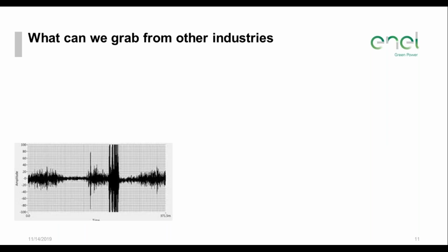For example, a very common technology in other industries is ultrasonic analysis. Using this tool, we can pick up the ultrasonic emissions - sound waves outside the human hearing range - which are emitted by equipment when arcing, tracking, and other electrical events occur. This is quite common in other industries, especially the fossil fuel industry, for substations, transformers, power connections. So should we start looking at this technology as a way to identify failures in inverters, and other assets, before they occur?